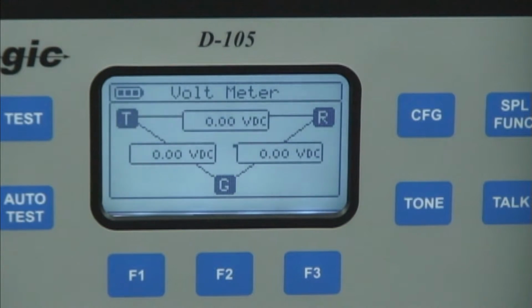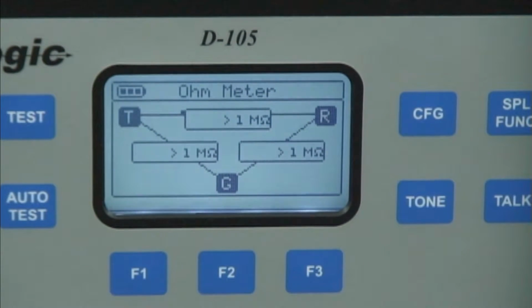The metering displays allow for viewing tip-to-ring measurements, tip-to-ground measurements, and ring-to-ground measurements all on the same screen without the need to press buttons. Resistive faults such as shorts, tip ground, and ring ground are easy to see on one display.